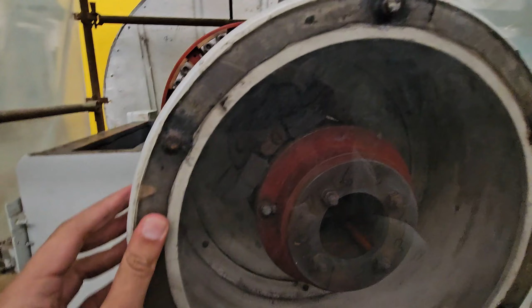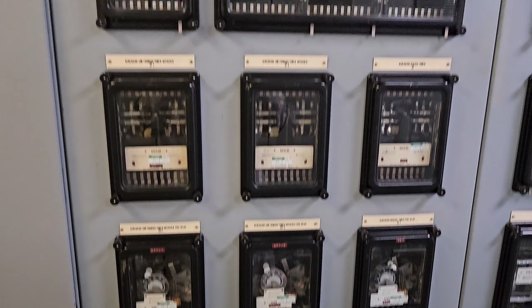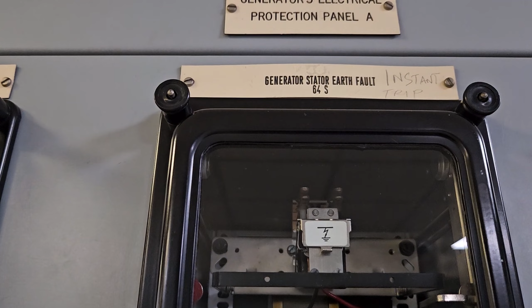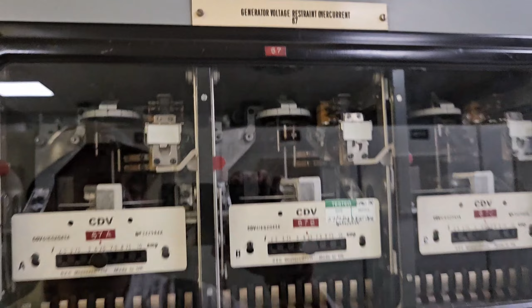Now let me show you the generator protection panel, what kind of protections we have in this generator. This is the generator protection panel, and as you can see, all protection relays are electromechanical relays. Nowadays these kinds of relays are not used. Here we have the generator earth fault relay, generator stator earth fault relay, guard relay. Downside we have generator voltage restrained overcurrent protection relays, generator differential relay, generator low forward power interlock relays, and generator low forward power interlock time relays. Then on the bottom we have the automatic synchronizing panel. So this is the generator protection panel.